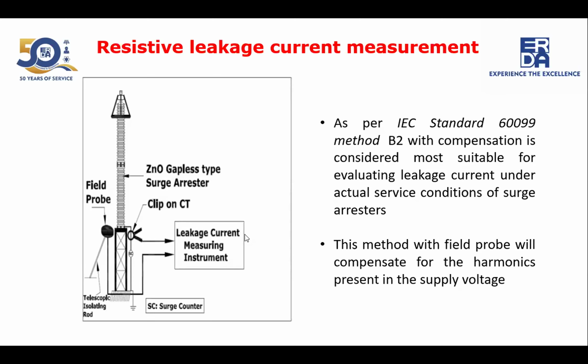We can see over here one surge arrestor has been connected. This one is the surge arrestor mounted on the metallic structure, and here a current transformer is connected, which is a part of the equipment. This one is the equipment leakage current measuring instrument, which measures the leakage current flowing through the surge arrestor. One field probe is also connected over here because whatever harmonics are there in the supply have to be bypassed or nullified. Otherwise, those harmonics may result in inaccurate readings of the measured leakage current. That is why this field probe has been connected.